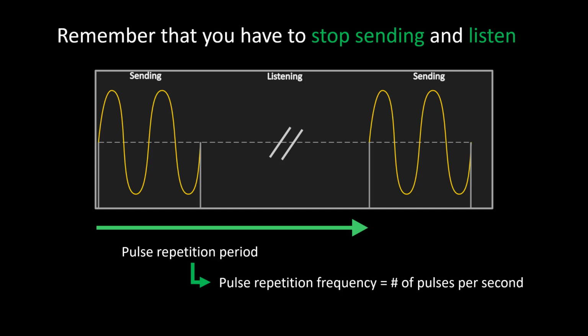One of the key elements that governs temporal resolution is the pulse repetition frequency. As you've heard, the transducer has to send a pulse of wavelength and then listen for a returning signal. The listening part is significantly longer than the pulse. The number of pulses per second is the pulse repetition frequency and depends on the listening duration, since the pulse length is fixed for each transducer.